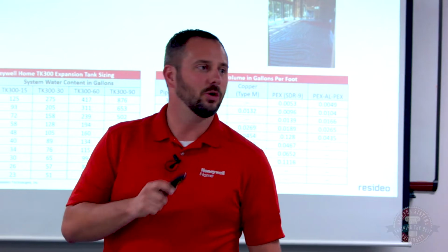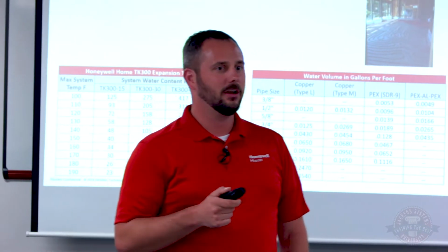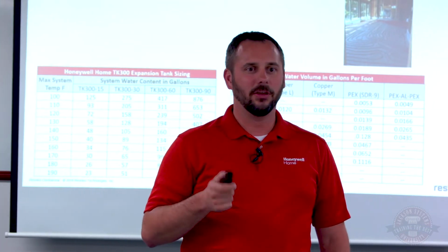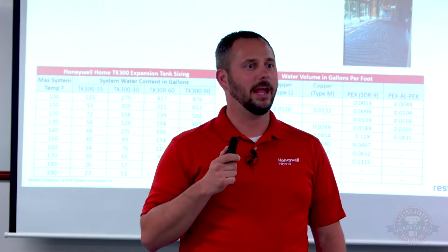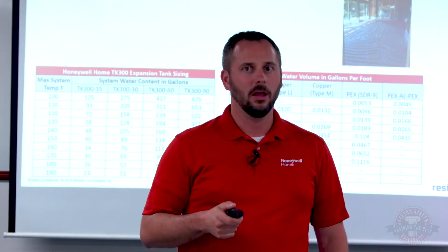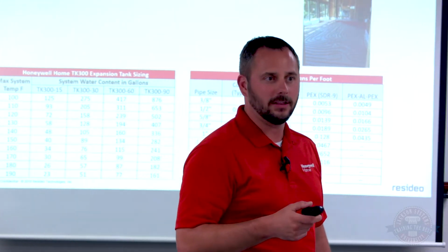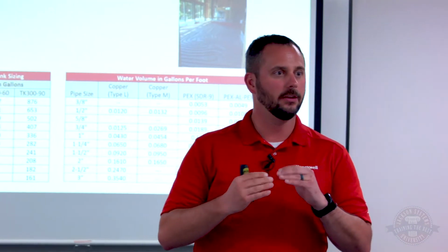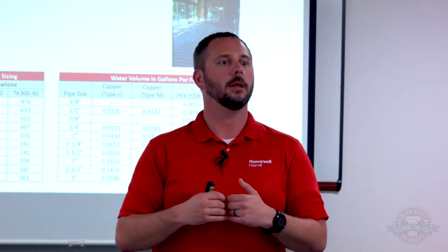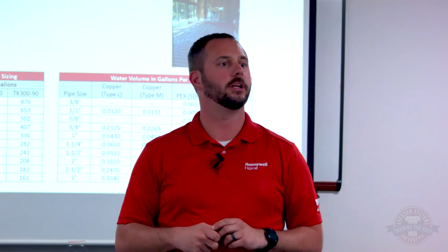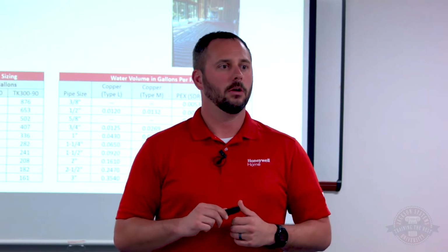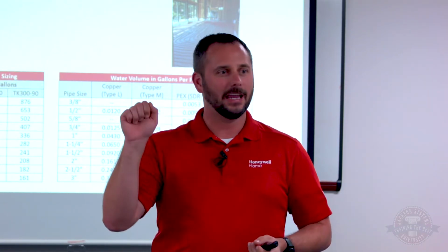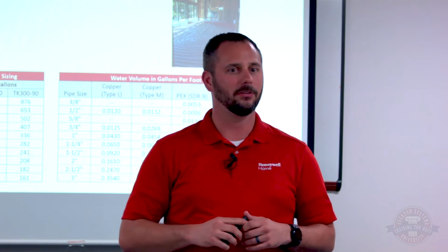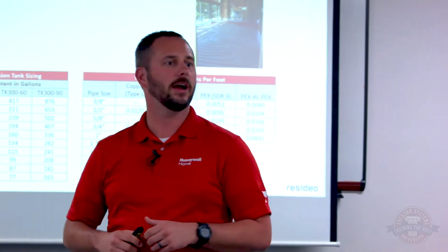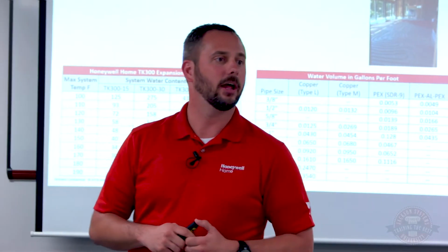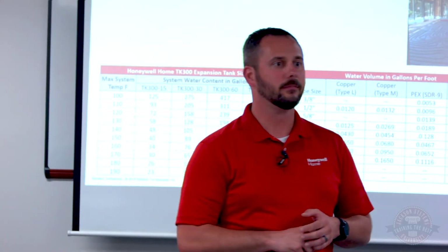But I'll caution you, if you use that as a check, you're letting air out. So if there's nothing wrong with the expansion tank, you have now let air out of the expansion tank. The only way you can ever get that thing back to where you want it is to disconnect it from the system and pressurize it with no water pressure on the other side. So knock against it and see if it's hollow first, because as soon as you press against that relief valve, you're letting air out of the back side of that.